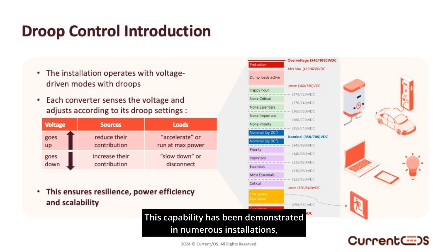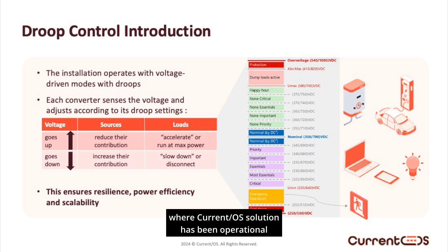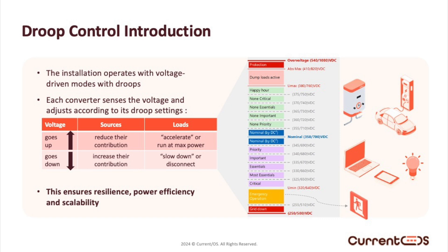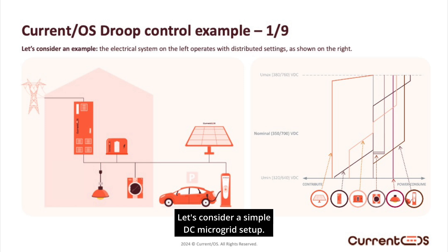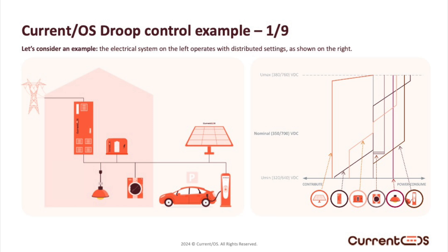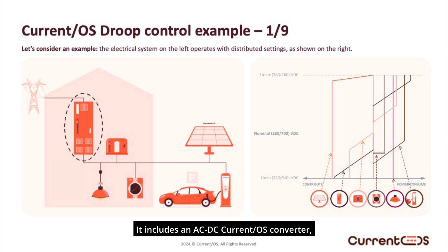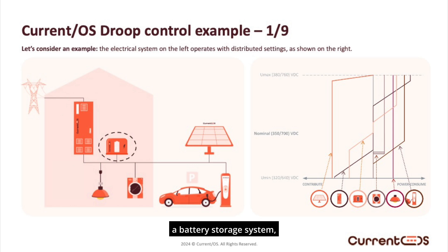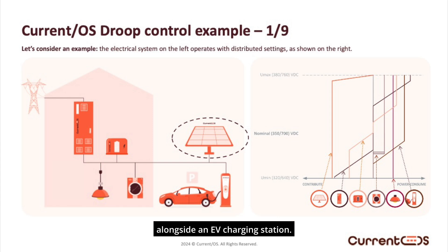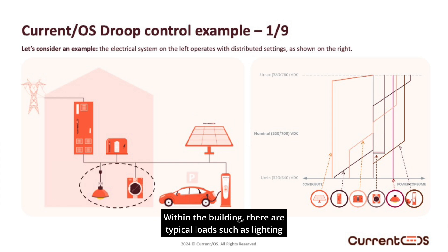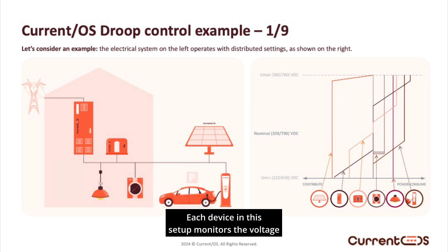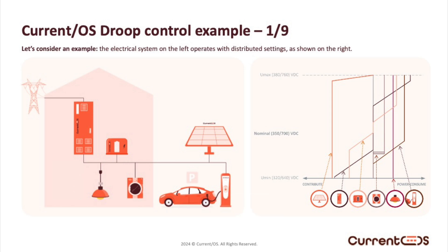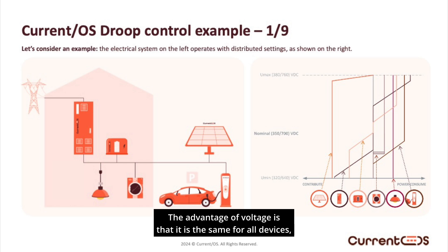This capability has been demonstrated in numerous installations where the Current OS solution has been operational for several years. To illustrate the concept with an animation: let's consider a simple DC microgrid setup. It includes an AC/DC Current OS converter, a battery storage system, and photovoltaic panels in the parking lot, alongside an EV charging station. Within the building there are typical loads such as lighting and a washing machine. Each device in this setup monitors the voltage on the common bus. The advantage of voltage is that it is the same for all devices, serving as a universal signal to guide their behavior.